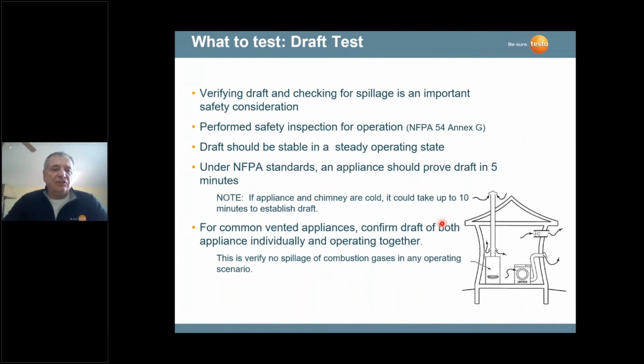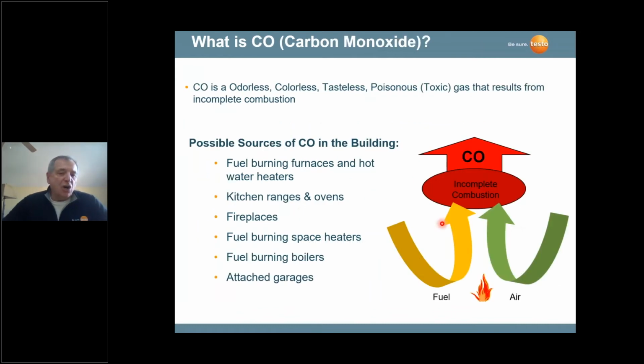Right? Draft is another measurement that we do in the analyzer. We measure draft to support the combustion process, to make sure that we have the right amount of draft pulling the flue gases out the stack. If we have too high of a draft, then we can pull too much heat from the combustion process. If we have too little draft, then we could start having backdraft and flue gas spillage, and certainly that's not a good thing in a home or a building.